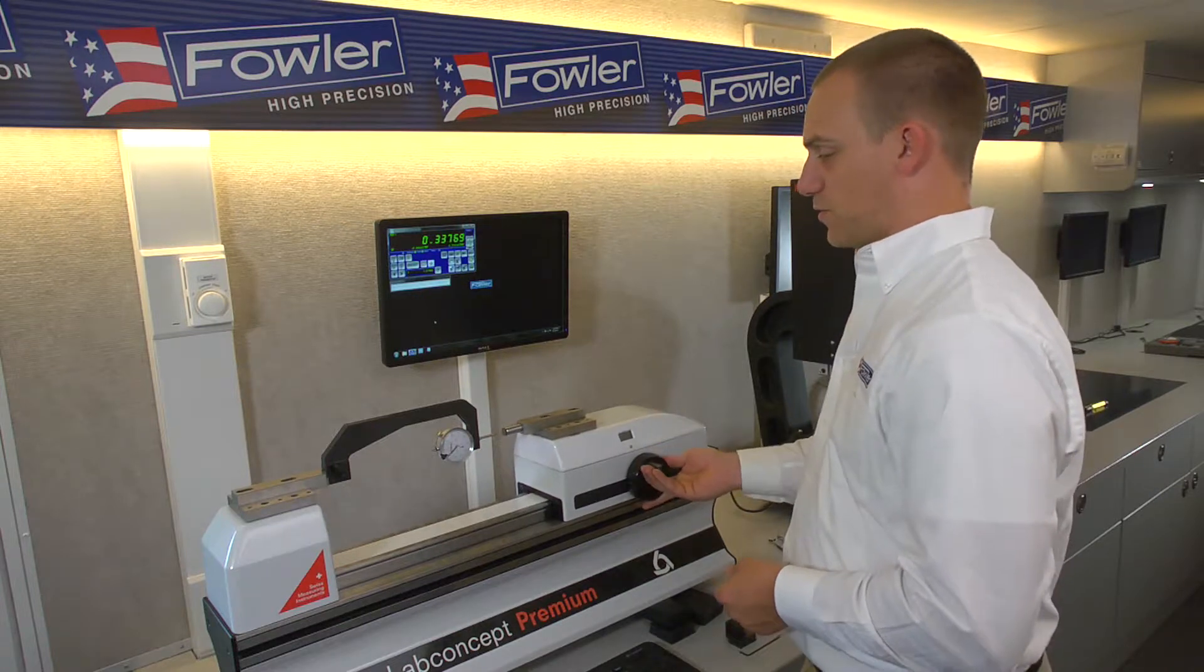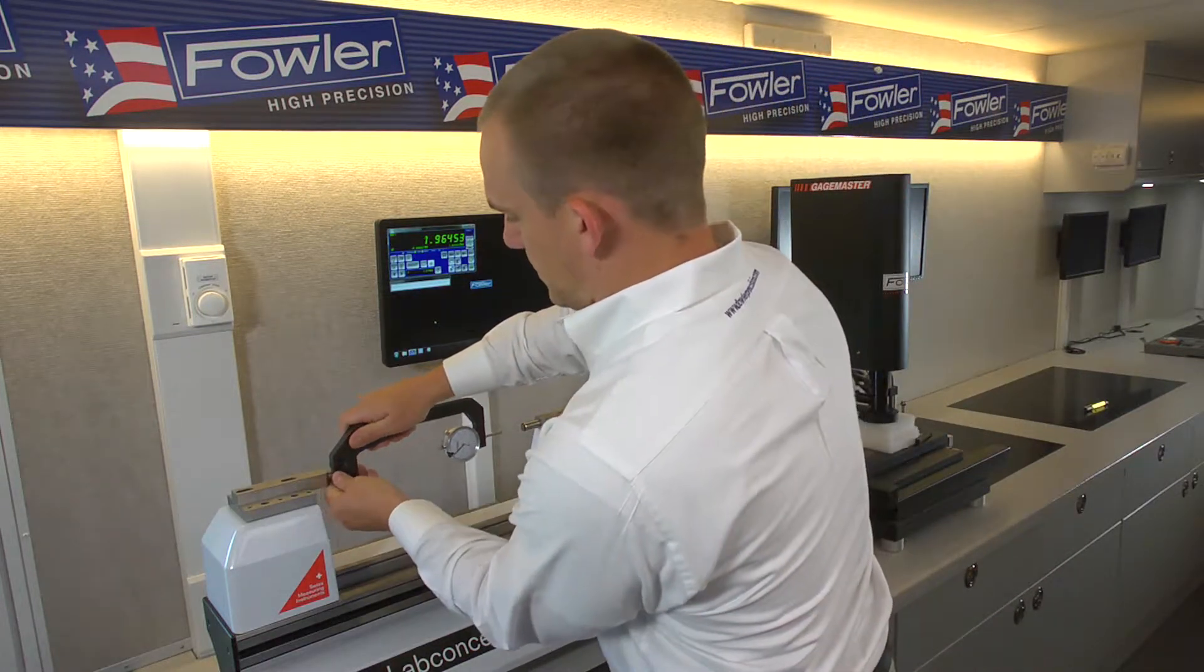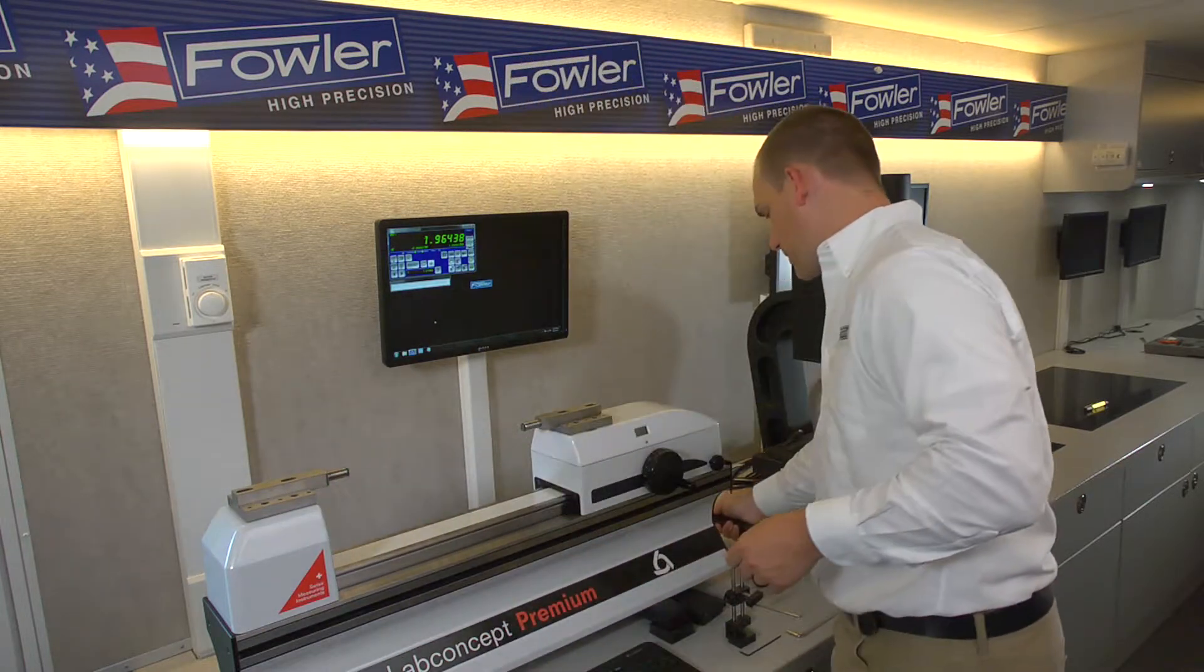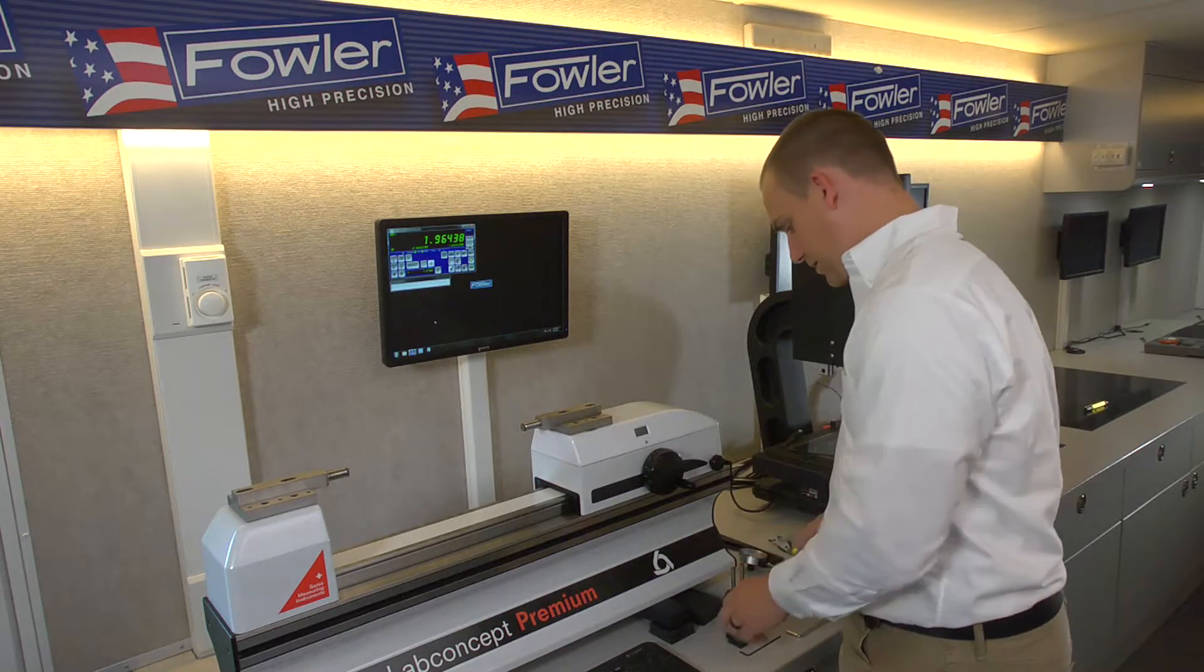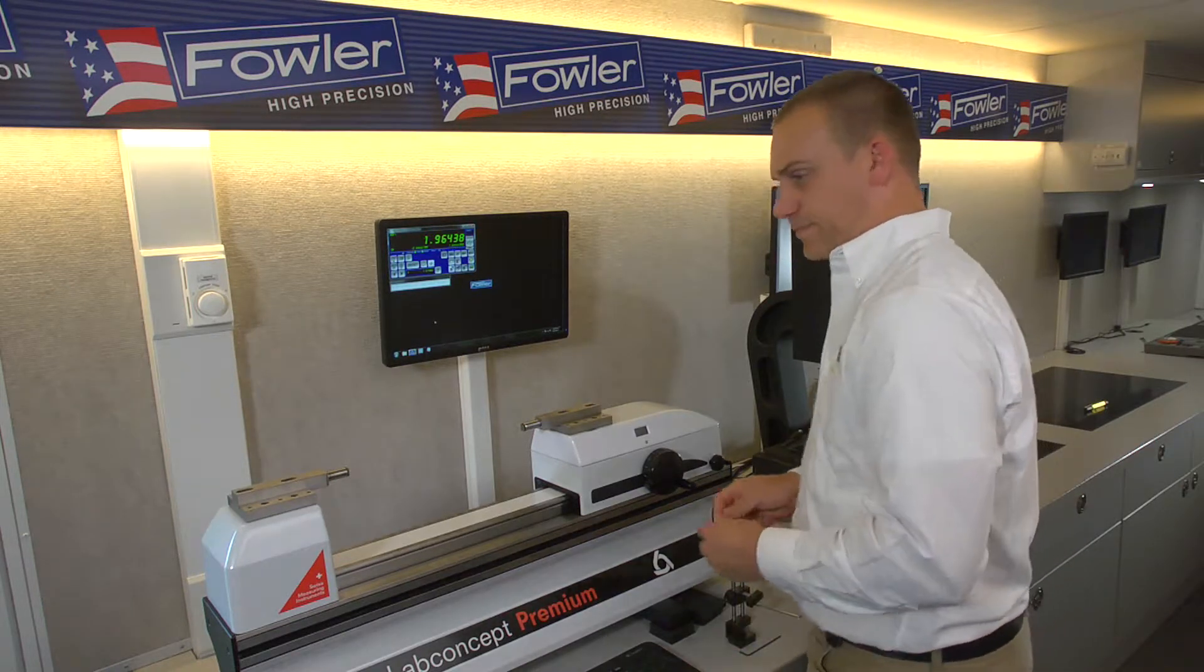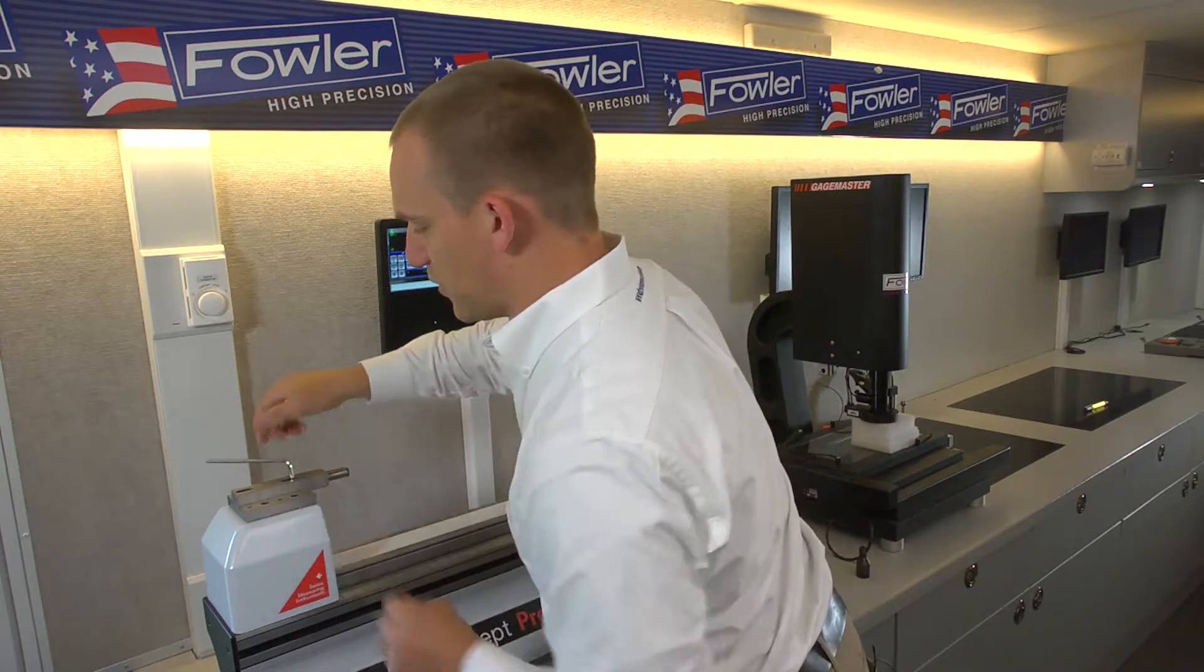I'm just going to break that down quickly. Now the test indicators require a little bit more equipment. For this we'd actually remove the fixed anvil using a five millimeter allen key.